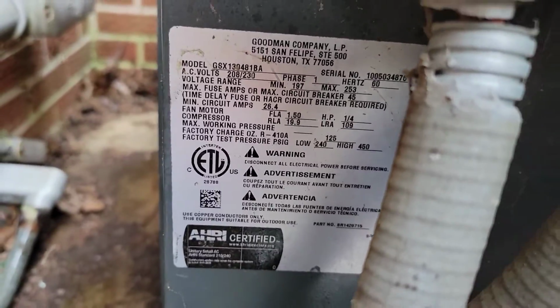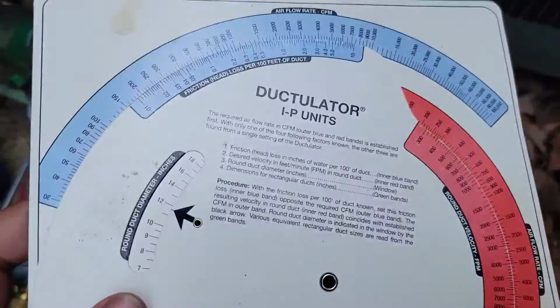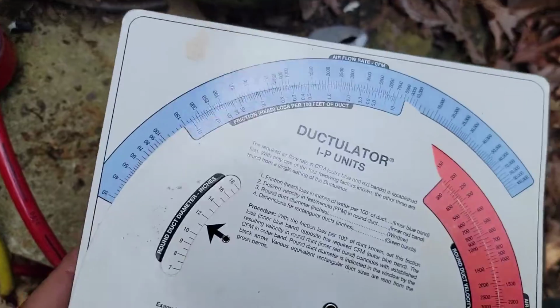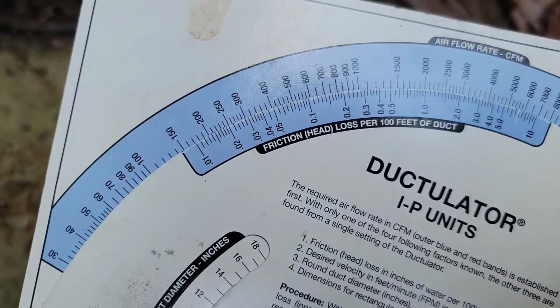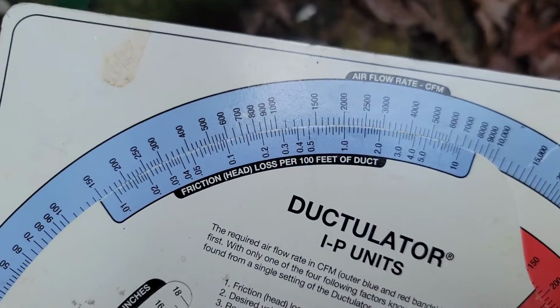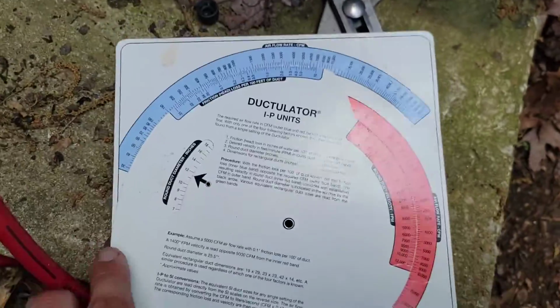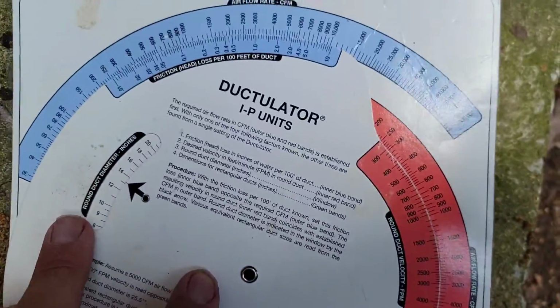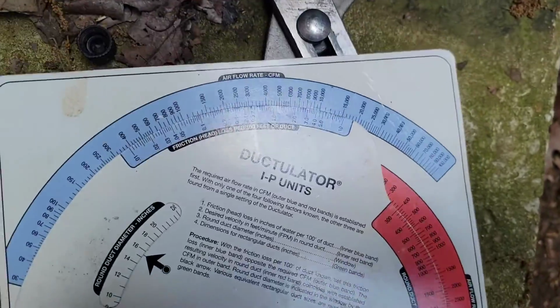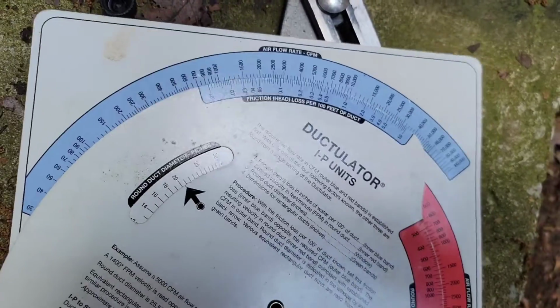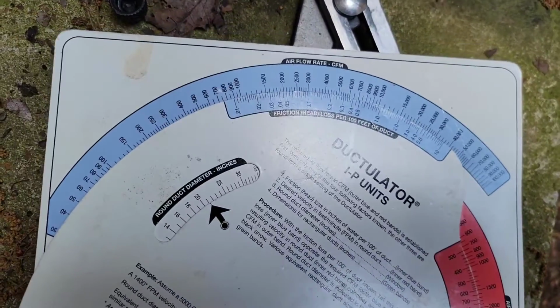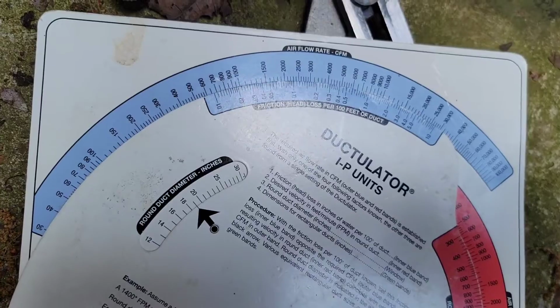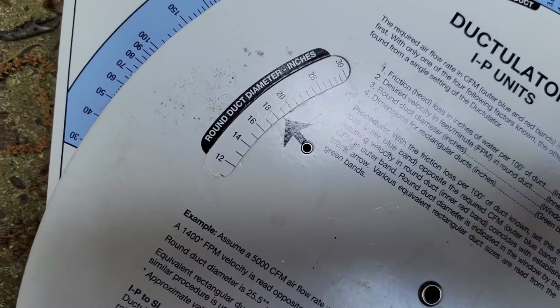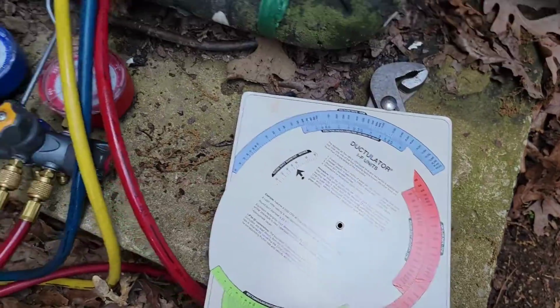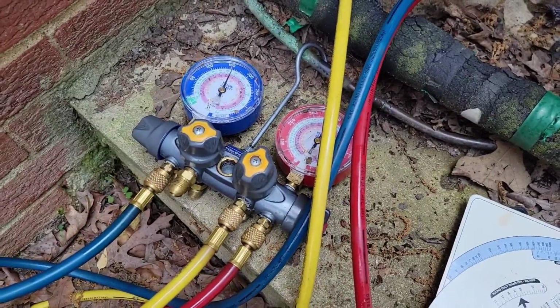This is a 4-ton unit and I need at least, on my Ductulator for a 4-ton unit, we'll line 0.05 up with 1600, okay? And I'm going to show you what that gets us. All right, we're going to line 0.05 up with 1600. See that right there, 0.05? We need 18-inch round duct diameter, a little over 18-inch. Let's go in and show you what's going on.